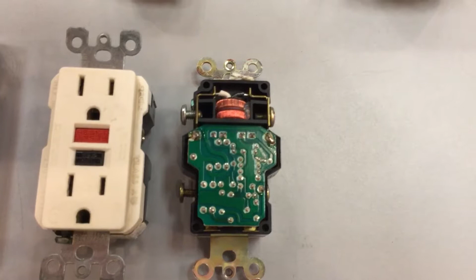But the small amount of current difference, maybe even as small as 10 milliamps, is enough, with the high turns ratio of this transformer, look at all those turns right there, to generate enough of a voltage to tell the electronics to cut the power, something's wrong. So this can be a real lifesaver, but it relies upon a transformer.